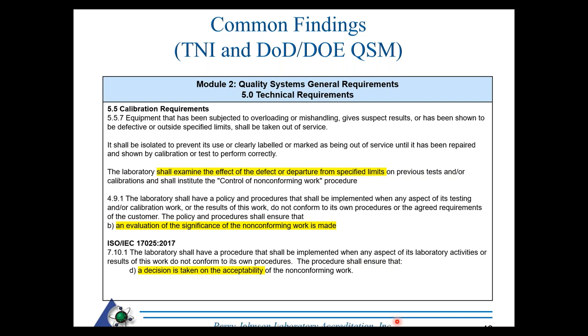Under calibration requirements, questions to ask when evaluating out-of-tolerance results: did it meet your tolerance even if the supplier's was tighter? Was it used at the out-of-tolerance range? For example, if a balance was measured at 10, 20, 60, and 100 and was out at 60, then you can't have used it above 20. Communicate required tolerances and calibration points in your procurement documents, and always document your evaluation of significance when out-of-tolerance conditions are identified.